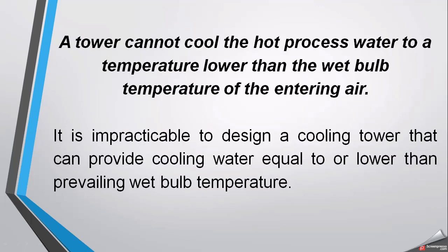Now we come to the explanation of cooling tower efficiency. A tower cannot cool the hot processed water to a temperature lower than the wet bulb temperature of the entering air — this is the thumb rule. The lowest possible temperature attained by the air leaving the tower equals the wet bulb temperature; normally it is higher. Therefore, it is impractical to design a cooling tower that provides cooling equal to or lower than the prevailing wet bulb temperature.